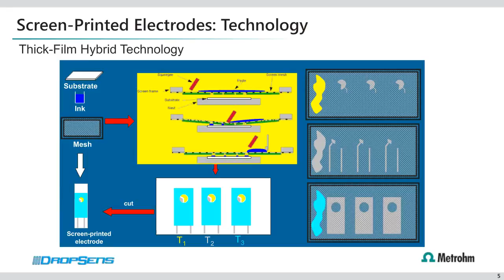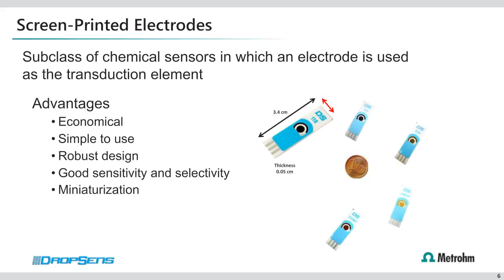The advantage of screen-printed electrodes when compared with conventional ones is that they are cheap to manufacture due to the technology employed that allows large-scale manufacturing. Their size and planar configuration simplifies working with them. Just a small drop of sample can be used to cover the 3 electrode system. This design is robust enough as we are avoiding systems where glass is used, for instance, the reference electrode. Through appropriate modification and method development, electrochemical sensors give good sensitivity and selectivity in their measurements. Electrochemical sensors and the instrument to perform the measurements allow miniaturization, and therefore portable and wearable sensing devices have become a reality.